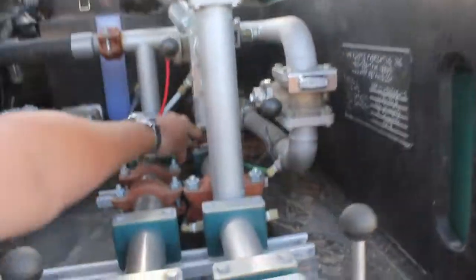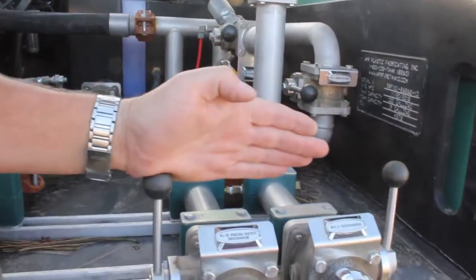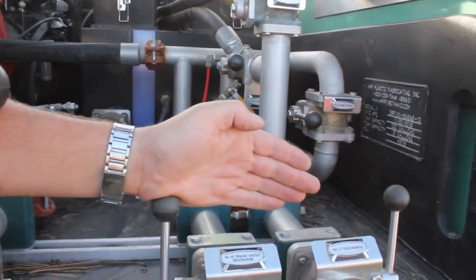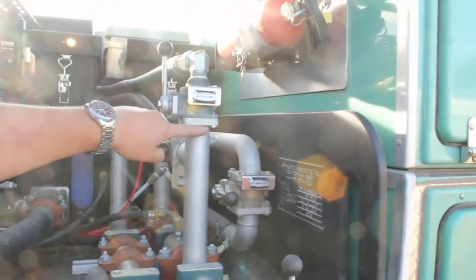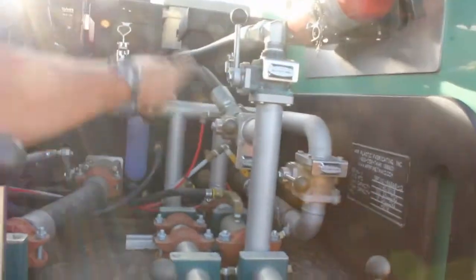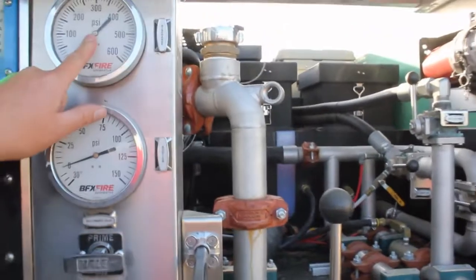This is a check valve right here. There's a check valve back here too. Forward of those check valves, I still have 200 psi. Coming up this line, I still have 200 psi — 200 psi going out the live reels. But why doesn't my gauge say 200 psi?